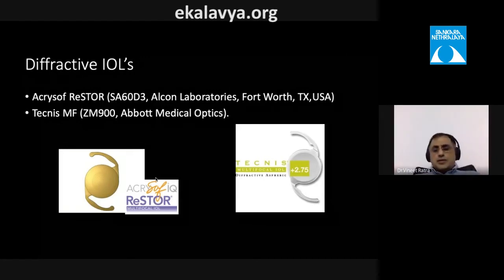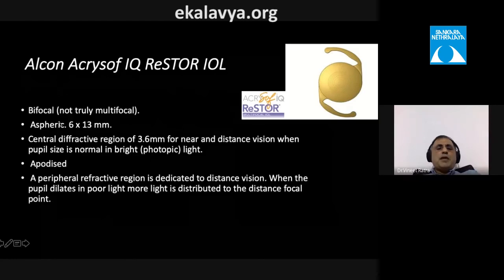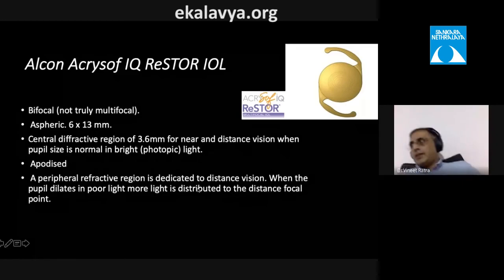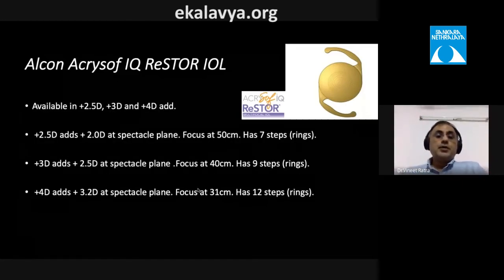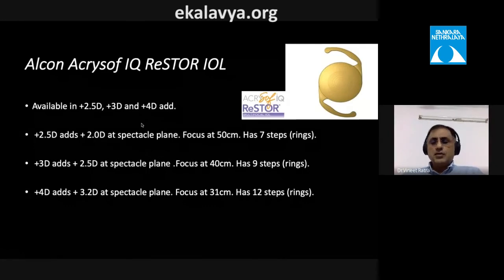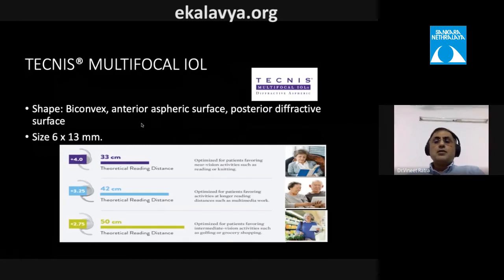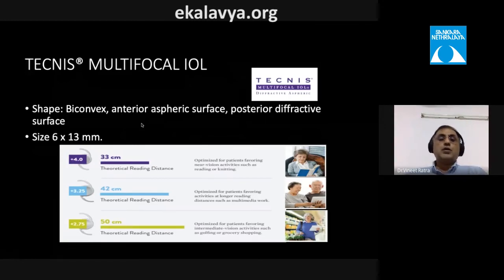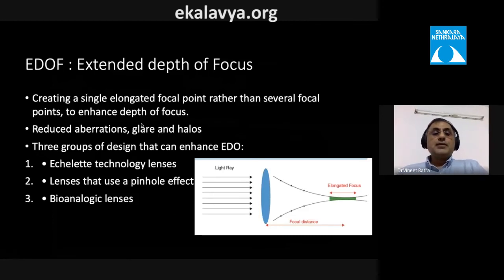The most well-known diffractive IOLs are the AcrySof IQ ReSTOR and the TECNIS Multifocal. The ReSTOR is technically bifocal, not multifocal: it has a central diffractive region of 3.6 mm dedicated to near, with the peripheral area dedicated to distance so that vision improves as the pupil dilates. It is available in +2.5, +3.0, and +4.0 diopter add powers. The TECNIS multifocal has a posterior diffractive surface and anterior aspheric surface, available in +2.75, +3.25, and +4.0 diopter adds.